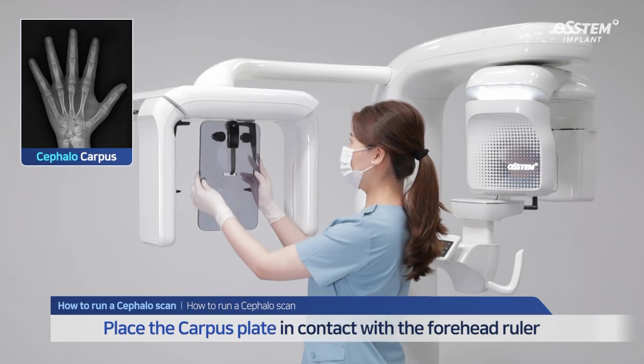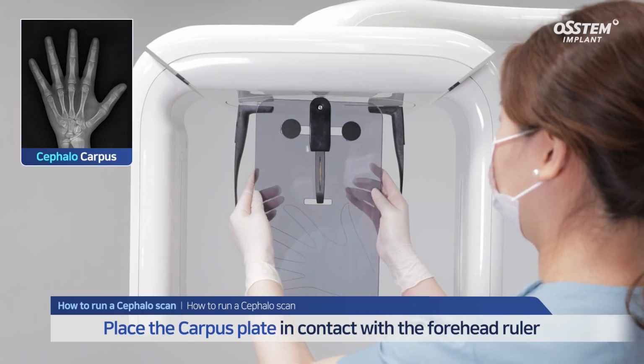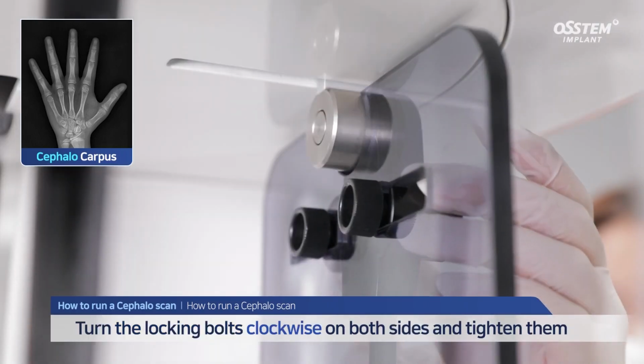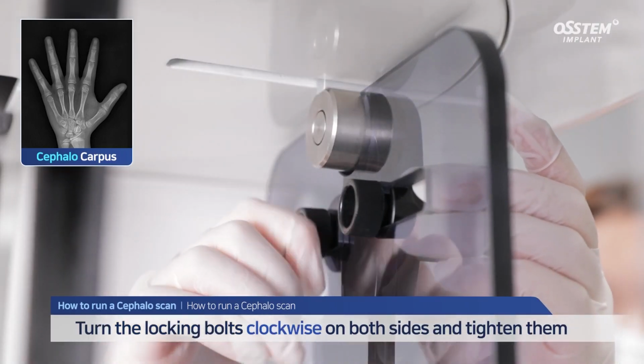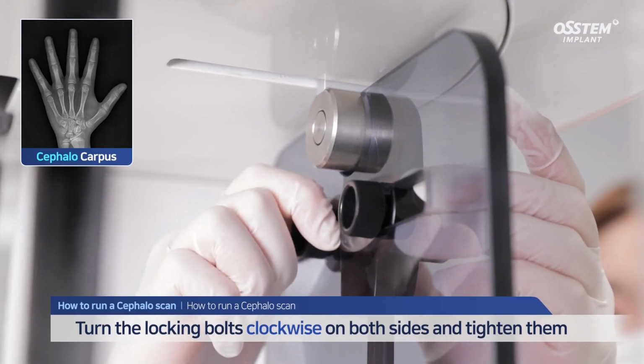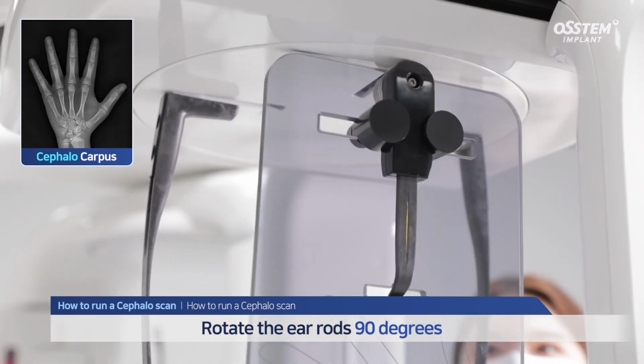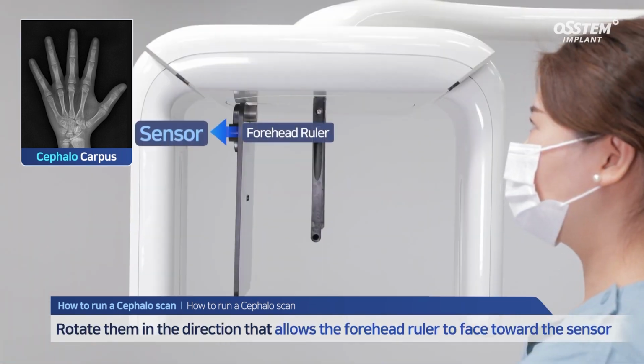Place the carpus plate in contact with the forehead ruler. Turn the locking bolt clockwise on both sides and tighten them. Hold the ear rods and rotate them 90 degrees. Rotate them in the direction that allows the forehead ruler to face toward the sensor.